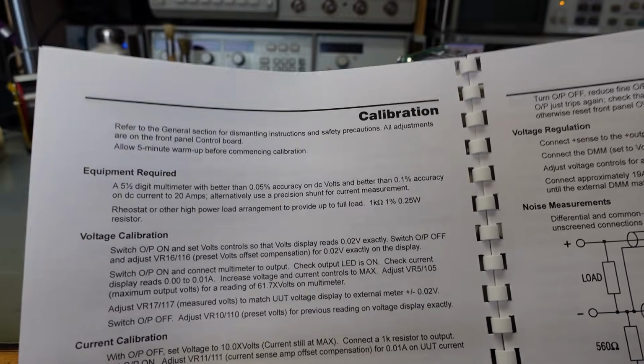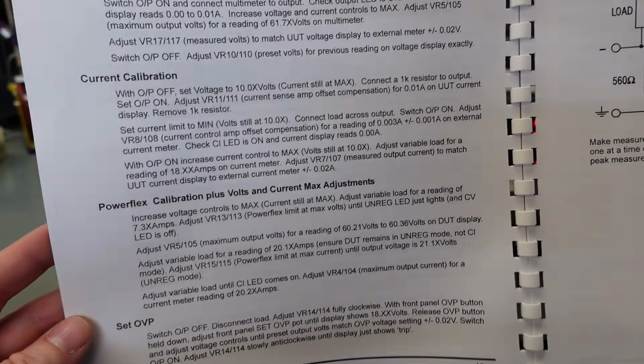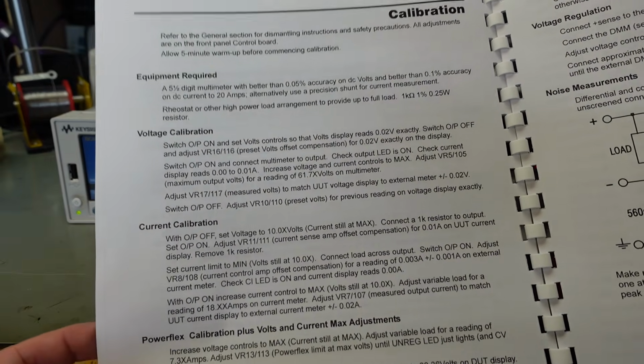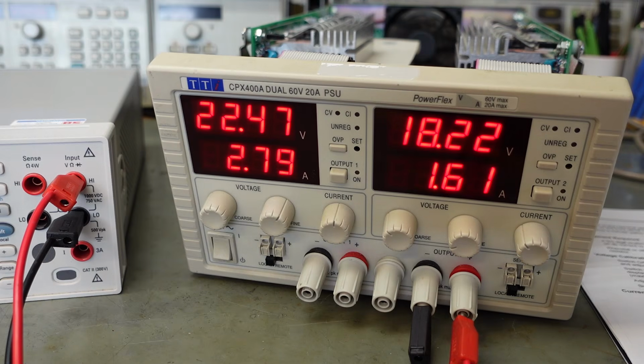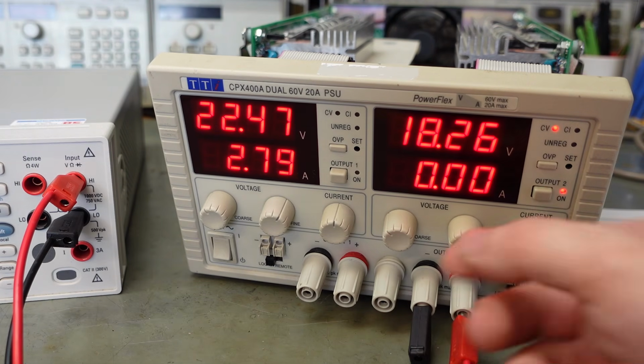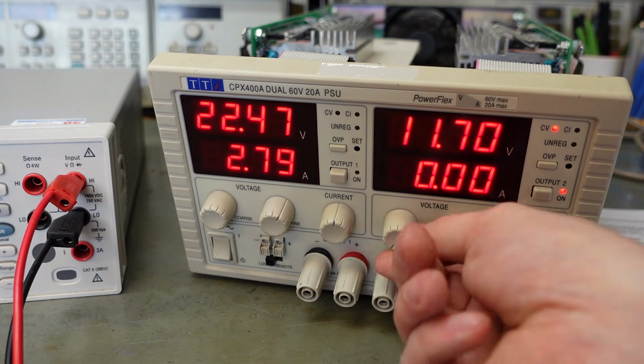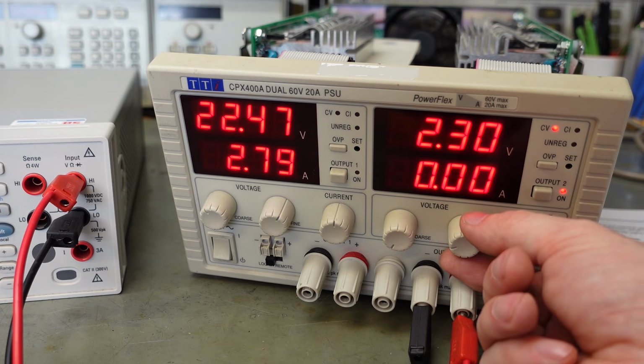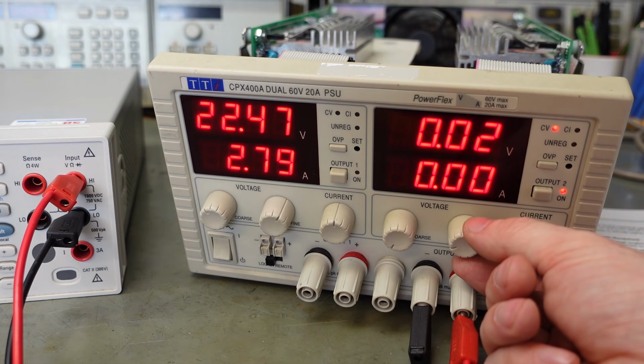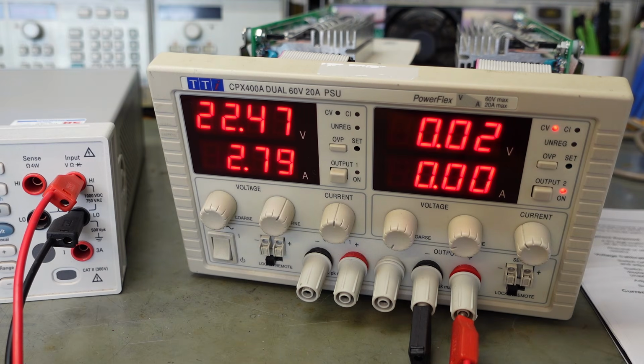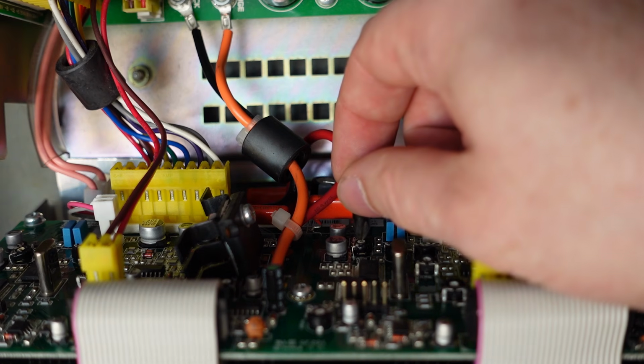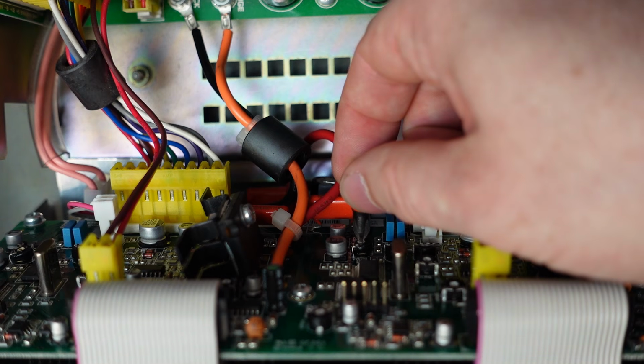Fortunately, the service manual tells you exactly what to do. There's only 1 or 2 pages of it, so I'm not sure I'm going to do all of it, mind you. Well, the first part of the calibration is to turn the output on. We need to adjust the voltage down to say 0.02 volts. It'll take a while to get there, mind you. Oh, look at that. Then we should turn the output off. Then we need to adjust a pot to bring this to say the same thing, 0.02. This is VR116 down here. Let's put a screwdriver tip in there.